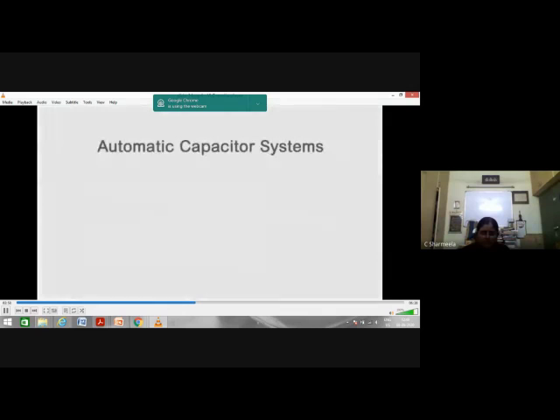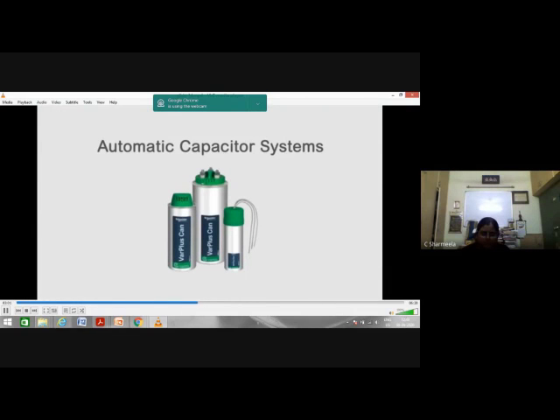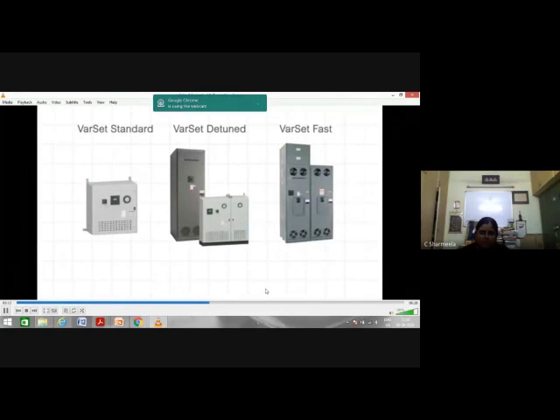The most cost-effective way to correct power factor is to use automatic capacitor systems. They're typically installed at the main distribution board or in the MCCs. The VARSET system is suited for small and medium-sized networks up to 1,500 kVA and in large installations up to 5,000 kVA.